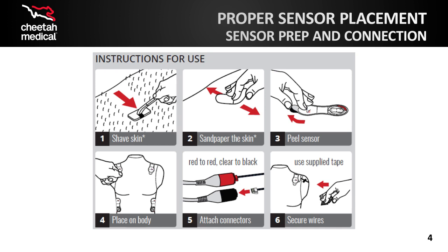Here are the instructions for proper sensor application. 1. Shave or clip according to hospital policy, body hair if needed. 2. Wipe the skin with sandpaper for optimal adhesion. 3. Peel the sensor. 4. Place the sensor on the 4 quadrants of the body. 5. Attach connectors. 6. Secure the lead cables to the patient using the supplied adhesive tape, Tegaderm, or other similar products which you have access to in your hospital.